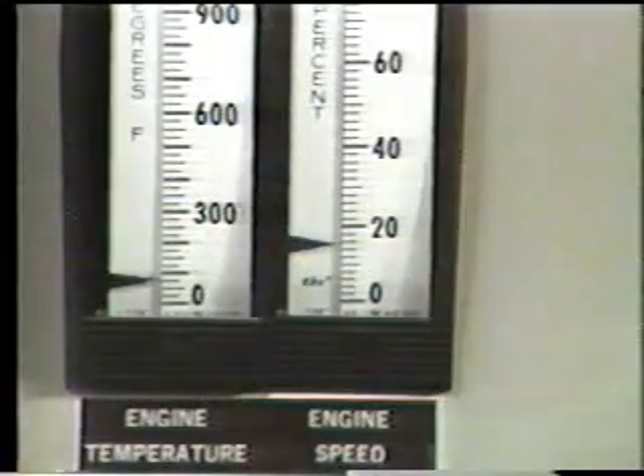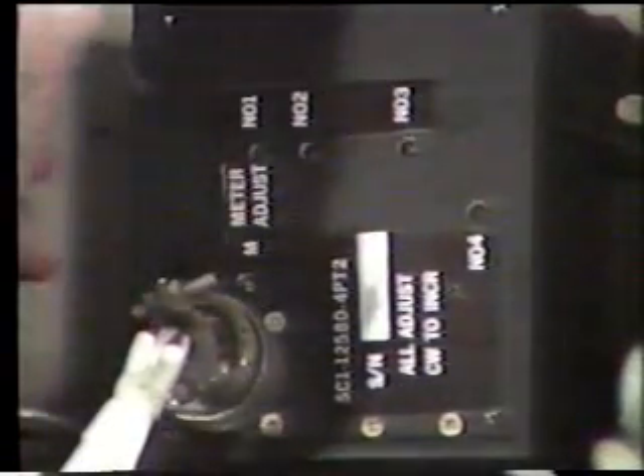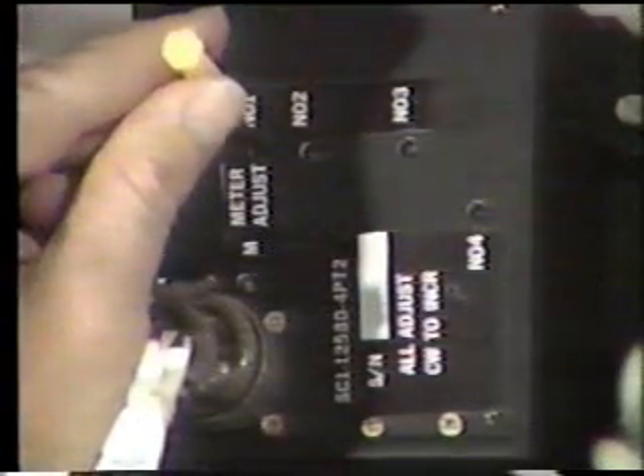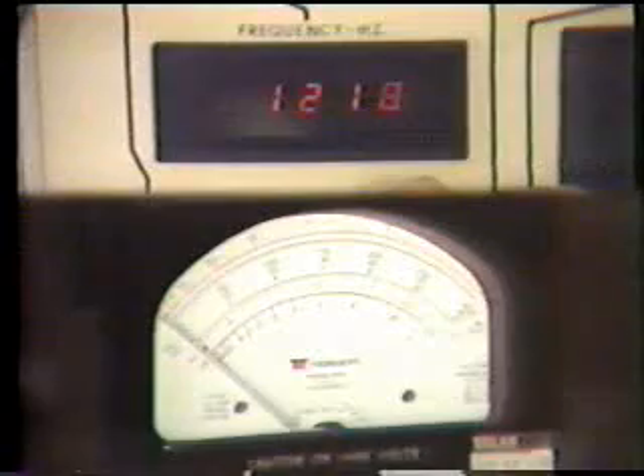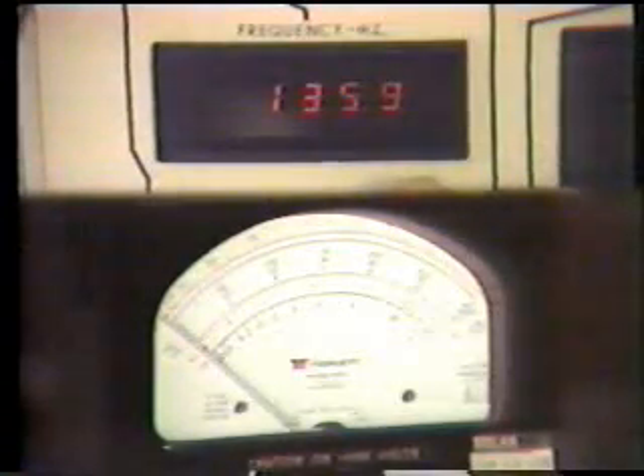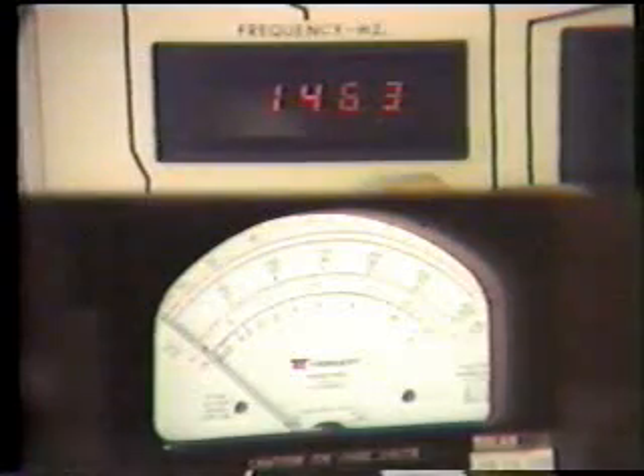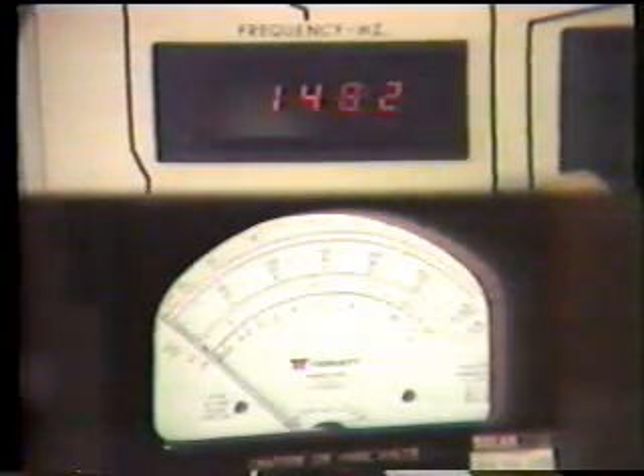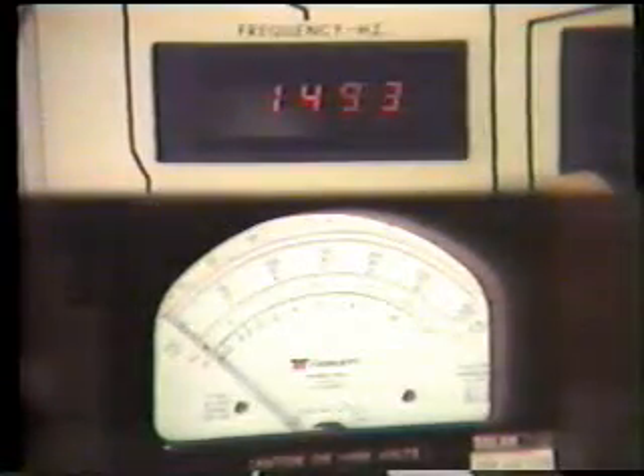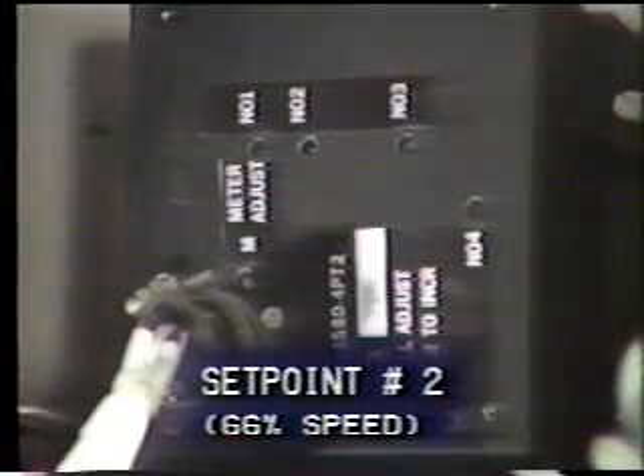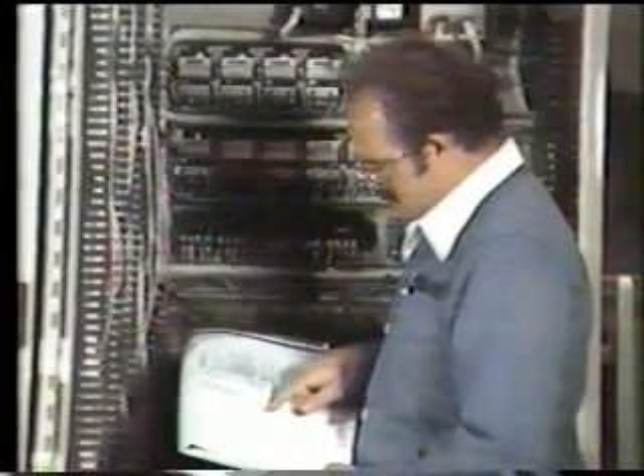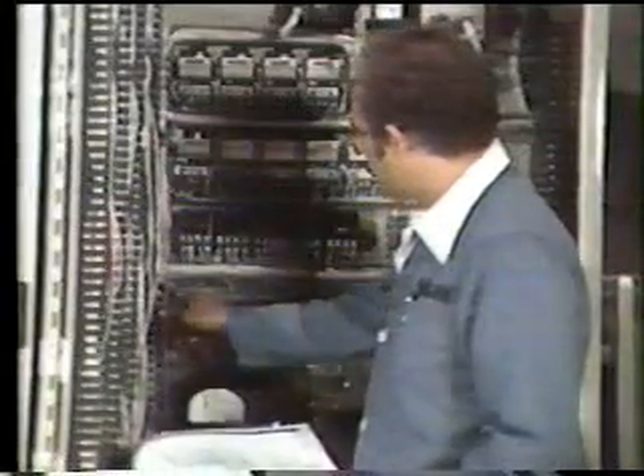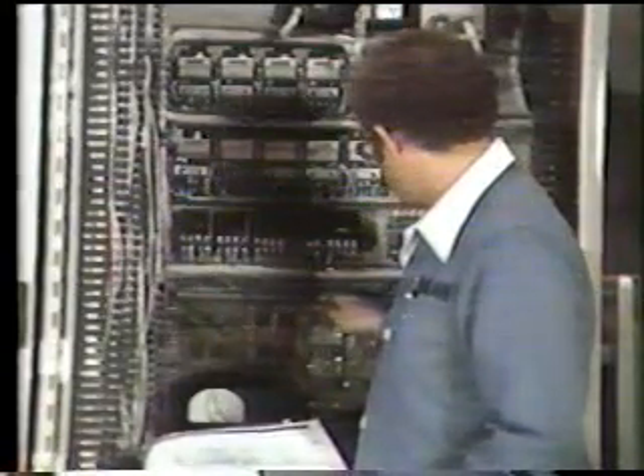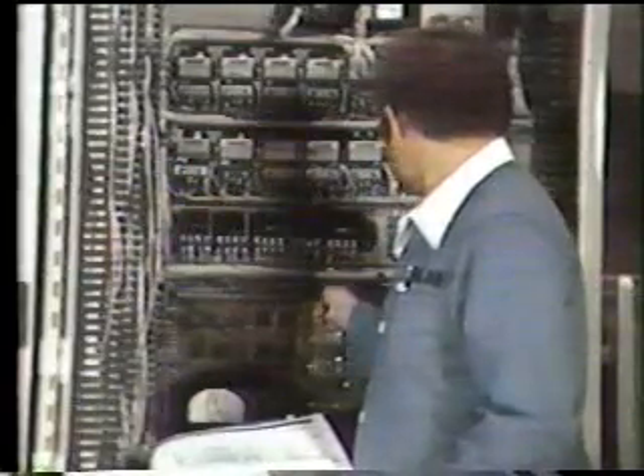If transfer does not occur at the correct frequency, adjust potentiometer number 1 on the control box face. Decrease and slowly increase the signal generator frequency and observe the VOM. Continue this procedure until the set point is correct. Next, verify set point number 2, the same procedures as before. Refer to the schematic and wire diagram for the proper terminal points in the console. Move the VOM test leads to the wires attached to the contacts for 66% speed.